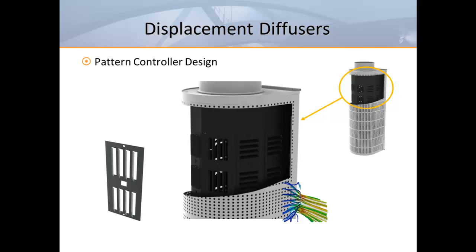Diffusers with adjustable air pattern controllers typically ship out in a default position that provides a standard radial air pattern. In order to allow easy access for field adjustment, the faceplates must be removable. Although diffusers with this feature are designed to be adjustable, it's still advisable to make product selections based on the standard radial pattern.